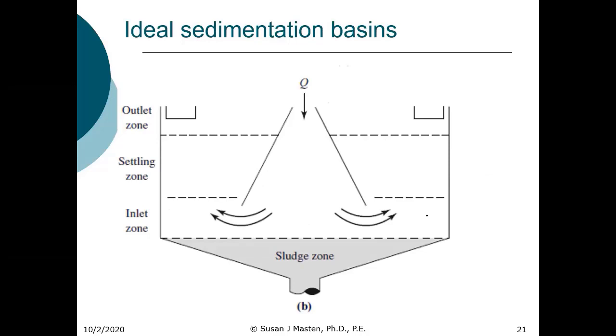We also have upflow clarifiers. Now these operate a little differently. As I mentioned, these have your mixer in the upper portion of the inverted cone. This is where you have the flocculation. So we'll just draw it as if we had the paddle wheels. We wouldn't have paddle wheels, but we have typically an impeller flocculator here. So we have flocculation here. And then the settling occurs out in the inverted cone here.